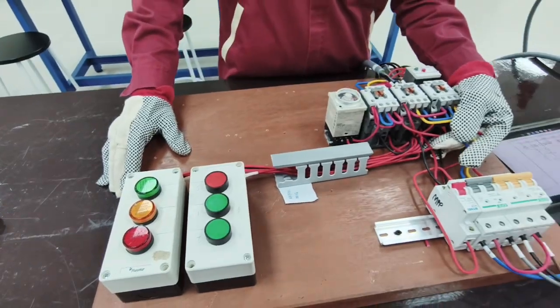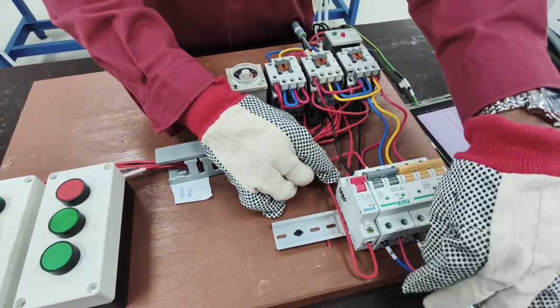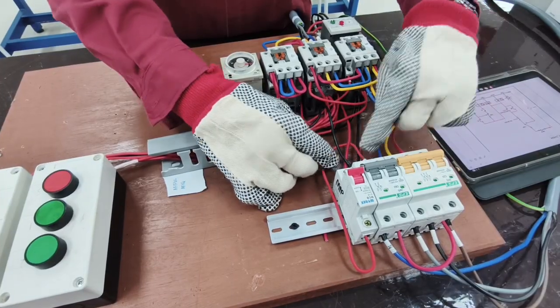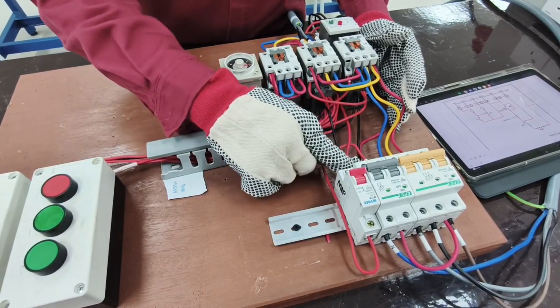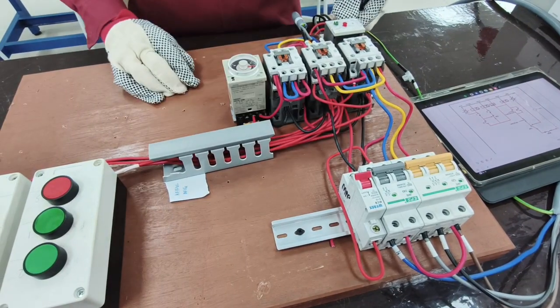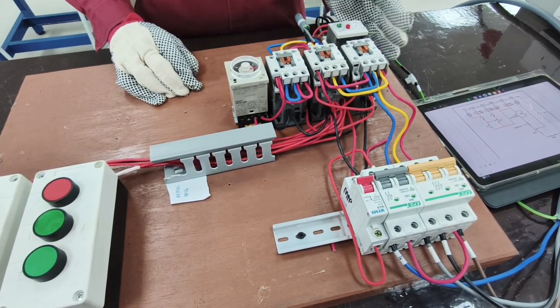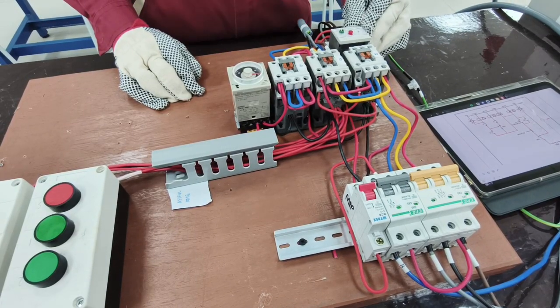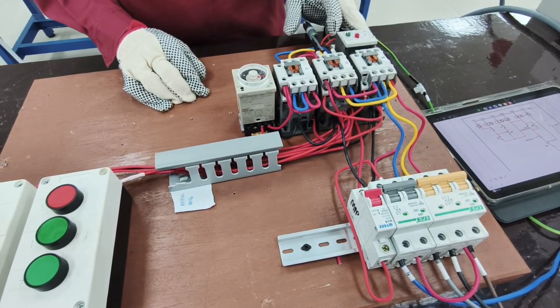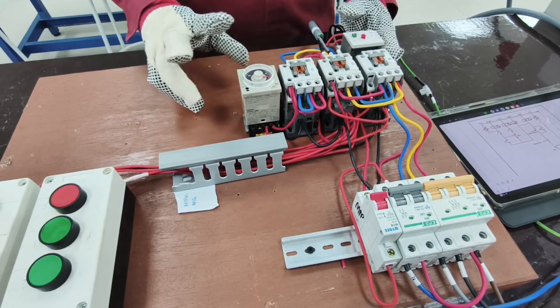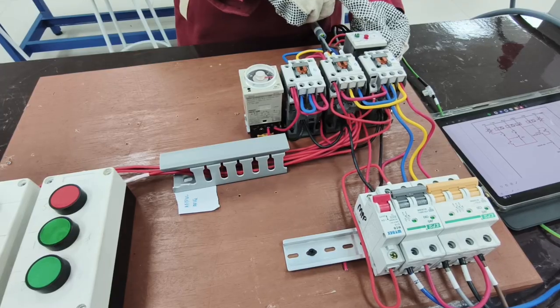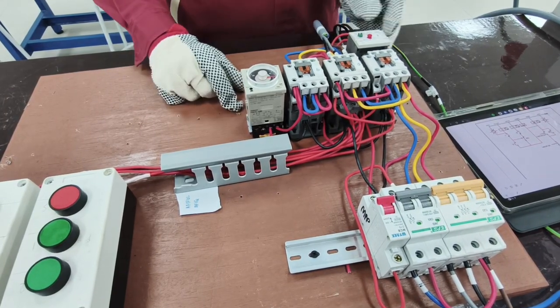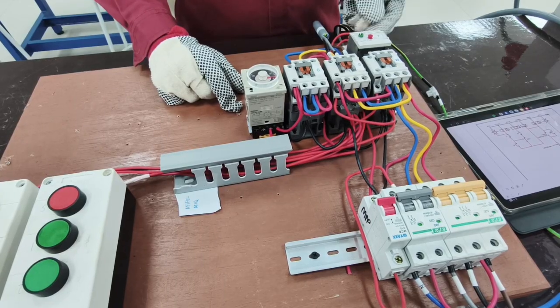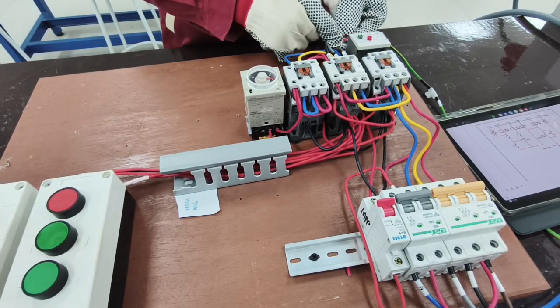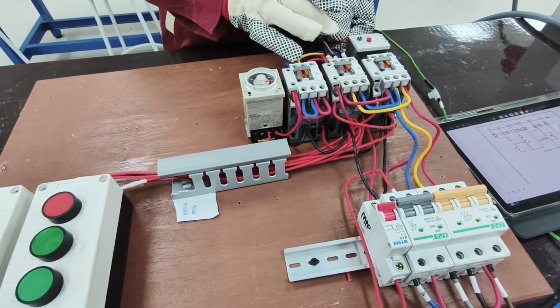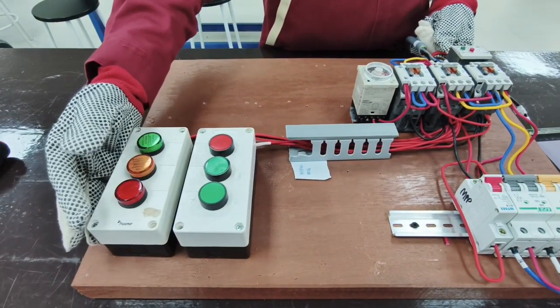Okay, so for the control circuit first, the supply will come from here, the two pole MCB, and then it will go up to the single pole MCB, and from the single pole MCB we go directly to the TOR. For the TOR we have the incoming 95, and then we will look to 97. From the TOR we have two outgoing, 96 and 98. Our 96 is normally closed and our 98 is normally open. The normally open, if the TOR is tripped, will light up this red indicator light.